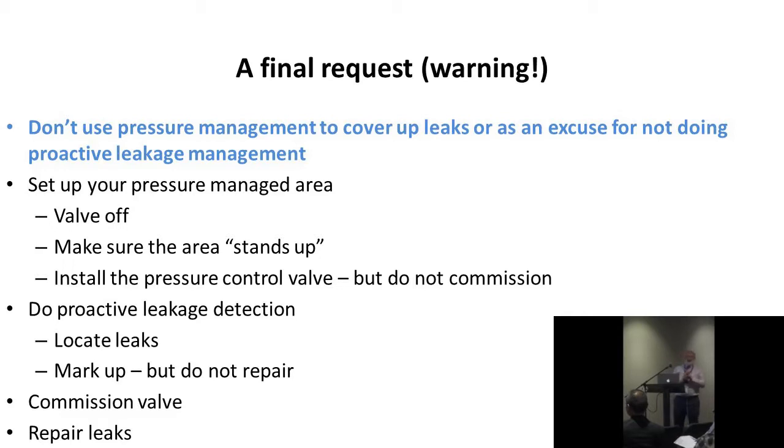And that is, my view is, do not use pressure management to cover up leaks or use it as an excuse for not doing proactive leakage management. I believe there's a lot of people in the world who think, I'll just stick a pressure management valve in and that'll reduce my leakage. If you've got leaks out there running on the network, the best thing you can do is go out there and find them and repair them, because they do not go away. There is no such thing as a self-healing leak.